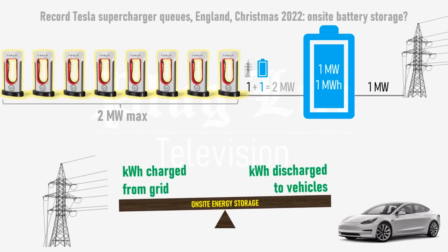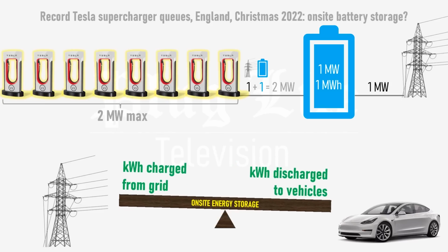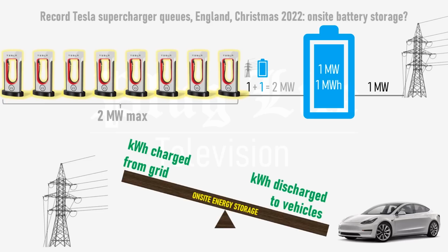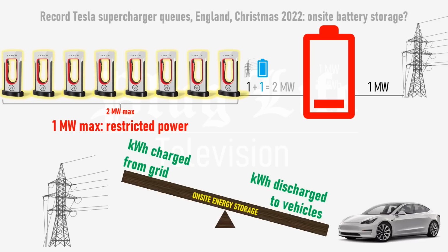However, if the cars discharge the battery before the end of the day, with the grid's capacity unable to recharge the battery during that time, then the battery will run flat, and the charging hub will have limited power supply, in this case being restricted to the 1 megawatt available directly from the grid.